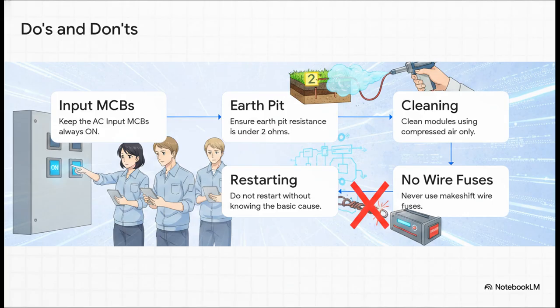They have to follow a very strict maintenance manual to prevent accidents. First, keep the input circuit breakers on. Next, regularly check that the earth pit resistance is under 2 ohms, otherwise that lightning protection might fail. Clean modules only with compressed air or soft cloths. They are strictly warned to never use makeshift wire fuses. And crucially, if the system shuts down, they must absolutely never restart it without identifying the root cause first.